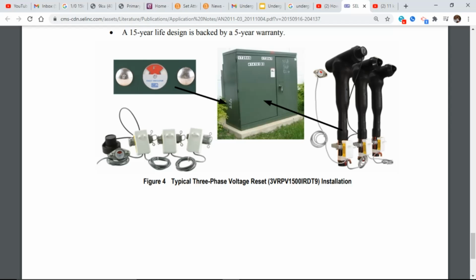That is not the case. If I put an amp meter on every single primary conductor that I've got out there to get fault indication, I'd be spending a ton of money. There is, though, something that happens with all conductors when they have a high amperage load on them, or even a low amperage load. What is given off by a conductor when it has current on it? We actually talked about it when we were doing locates in 60 hertz yesterday. Magnetic field. It gives off a magnetic field, exactly. All that's inside these indicators right here is an opposite or opposed magnet. Once the magnetic field on the conductor gets too high, it trips the indicator.